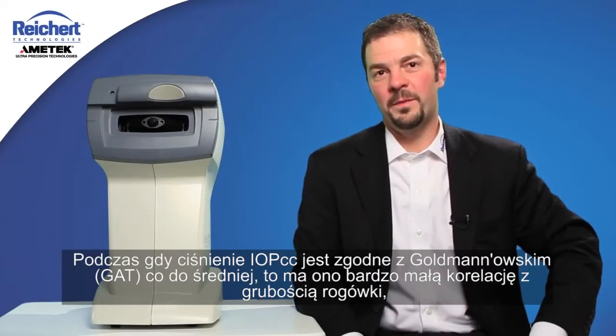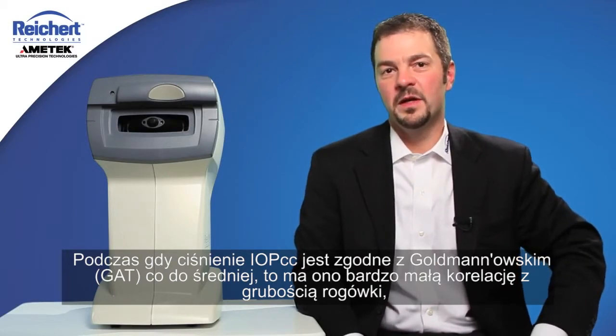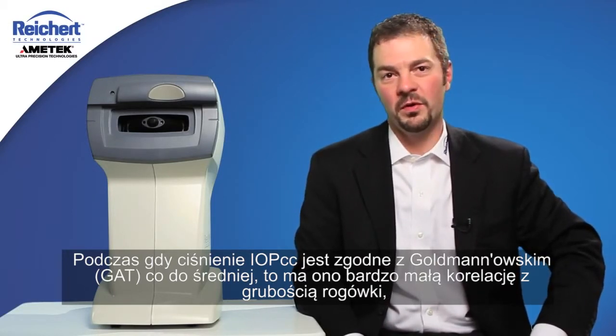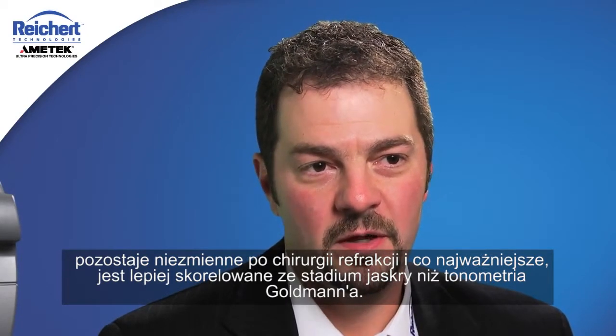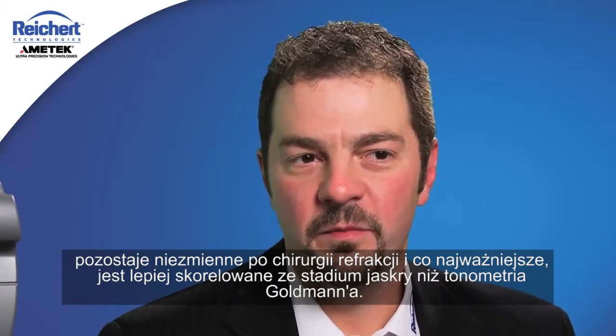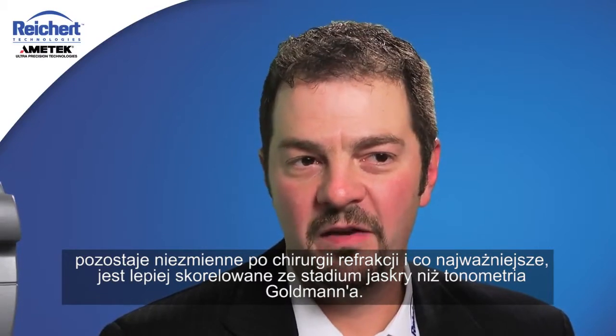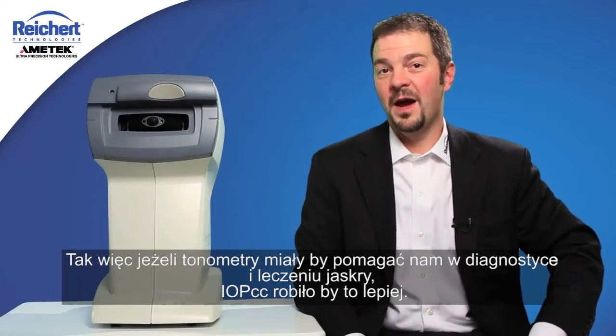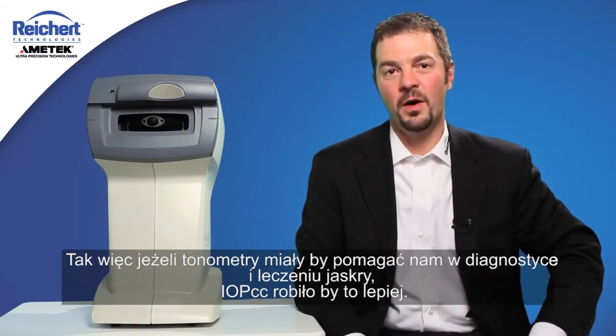While the IOPCC measurement agrees with Goldmann on average, it has very little correlation with corneal thickness, it stays fairly constant after refractive surgery, and most importantly it is better correlated with the status of glaucoma than Goldmann tonometry itself. So if a tonometer is supposed to help us diagnose and manage glaucoma, IOPCC does it better.